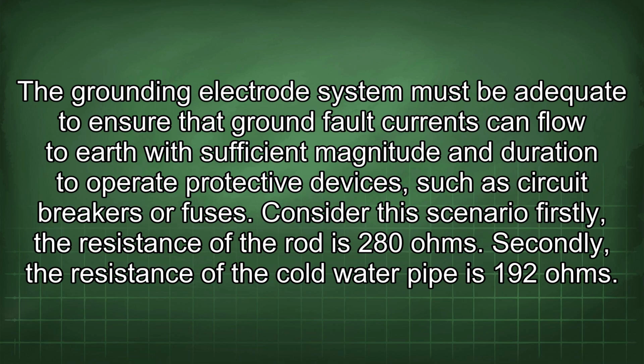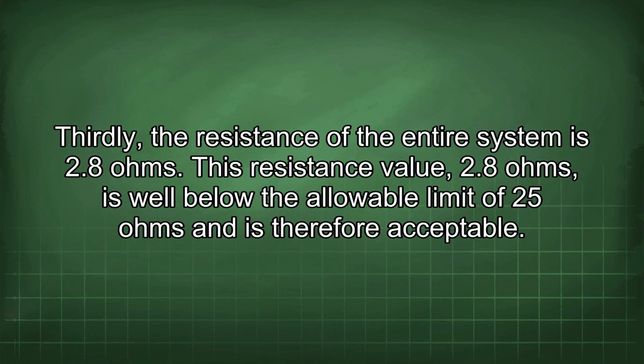Consider this scenario. Firstly, the resistance of the rod is 280 ohms. Secondly, the resistance of the cold water pipe is 192 ohms. Thirdly, the resistance of the entire system is 2.8 ohms. This resistance value, 2.8 ohms, is well below the allowable limit of 25 ohms and is therefore acceptable.